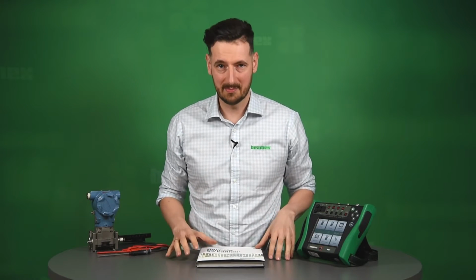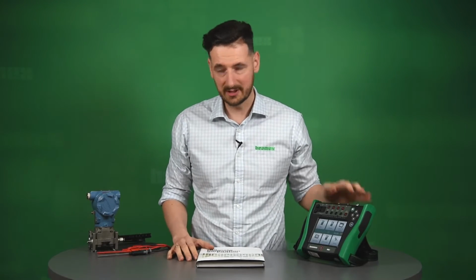Beamex, together with ISA, decided to put this video together to show you how you can calibrate a pressure transmitter. What we're going to do is have a documented calibrator, a pressure transmitter, sets of leads and a pressure generation, and we're going to show you how you can calibrate and trim the transmitter.